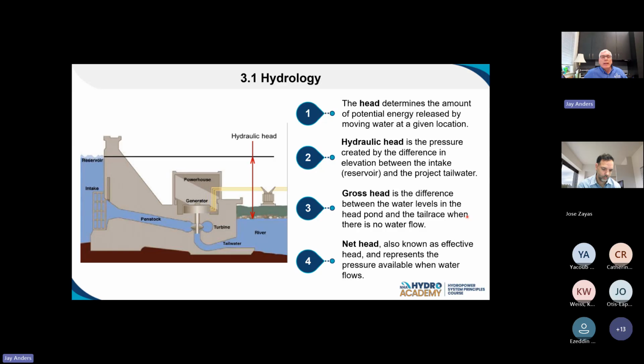It takes into account any losses or anything else. It's telling me what's available right there to my turbine itself. And hydraulic head is just that pressure created by the difference in elevation, between the intake and the project's tail water. So where you're measuring and what you're accounting for is what goes into these different types of heads. I think the mechanical engineers are just trying to confuse us electrical guys more than anything else.